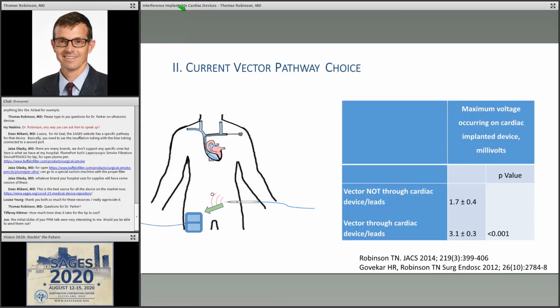What we learned from Amin is that even though we call it a monopolar instrument, it's bipolar because there's a dispersive electrode and an active electrode. The current travels through the patient between the tip of this tool and the dispersive electrode. It actually travels back and forth because it's alternating current. So you don't want to place your dispersive electrode up on the shoulder so that the current travels up through the pacemaker device, so it disrupts the device. You want to put it so that the current is routed away from either the defibrillator or pacemaker.